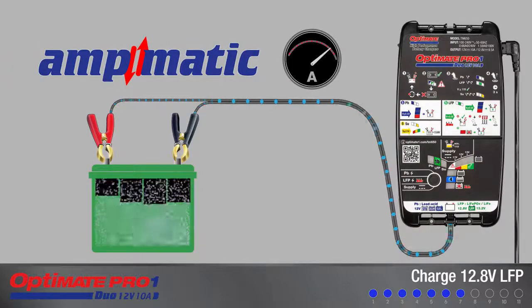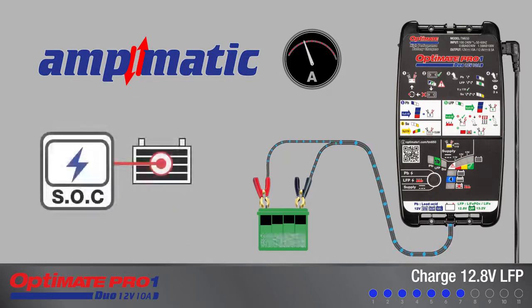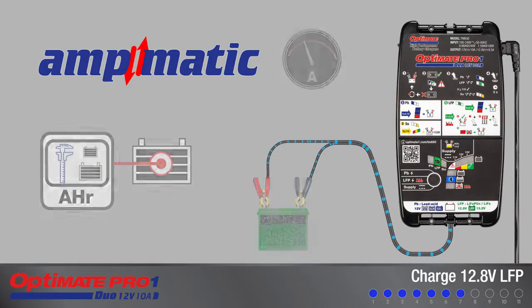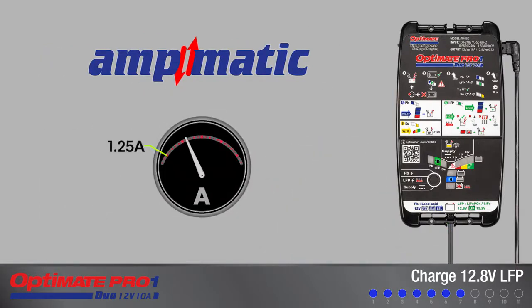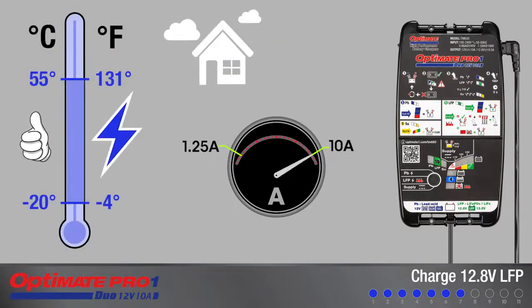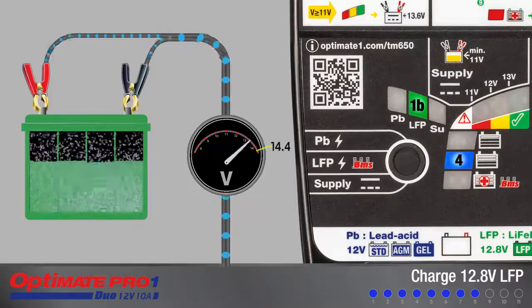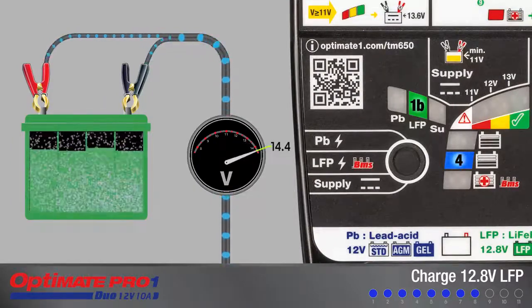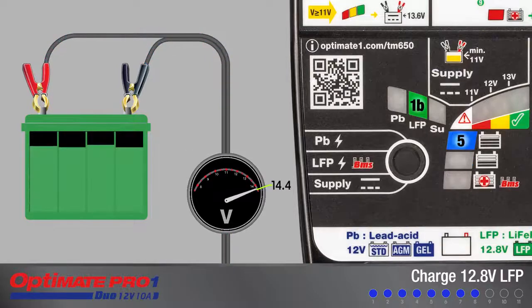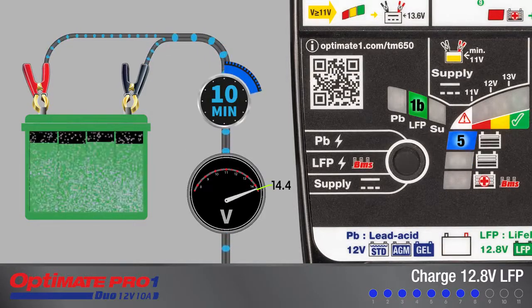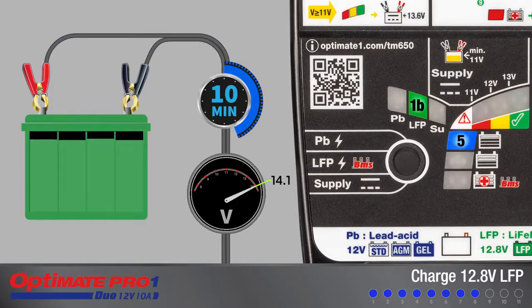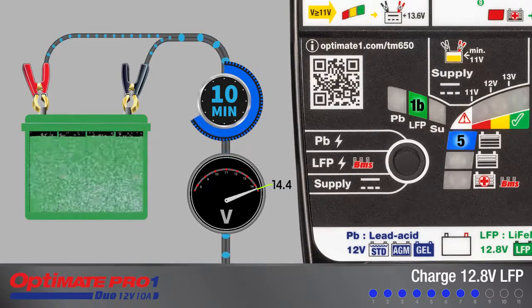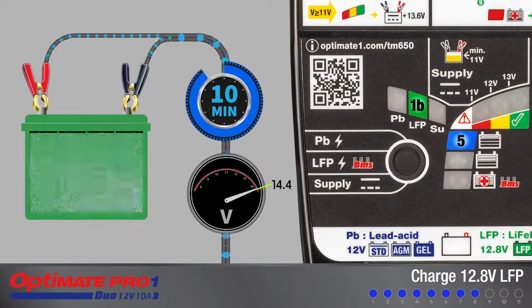The AmpMatic charge program automatically determines the most efficient rate of charge current for the connected battery. It accounts for its state of charge, state of health, and electrical storage capacity. The delivered current may be anywhere from 1.25 amps to 10 amps within the safe ambient temperature environment. Charging continues until 14.4 volts is reached, after which the AmpMatic current control program delivers pulses of current for a period of 10 minutes, with voltage cycling between 14.1 and 14.4 volts to equalize the individual cells within the battery.